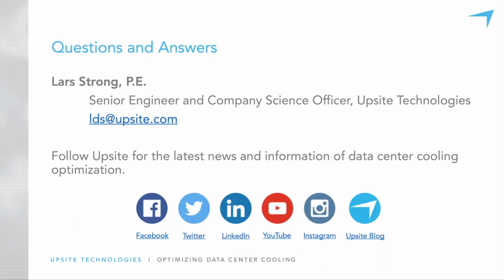a liquid-cooled facility is more efficient than even an airflow optimized cooled data center. But there is usually significant room for improvement with air-cooled facilities. We're seeing PUE numbers of air-cooled facilities in the 1.1s, or the 1.2s, 1.3s; 1.2s are not uncommon. So that's a very efficient facility, and a number of things have to be done to achieve that. So that's about as much as I think I can give you. I'd be happy to discuss this offline and get into more detail with you if you'd like.